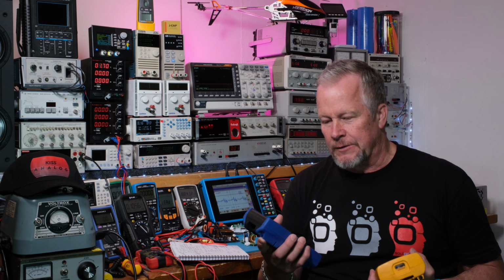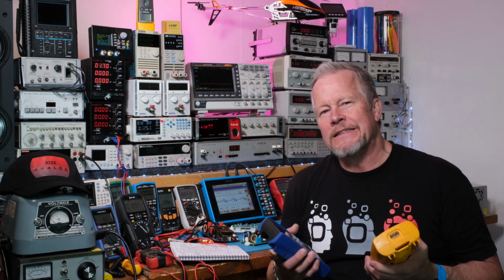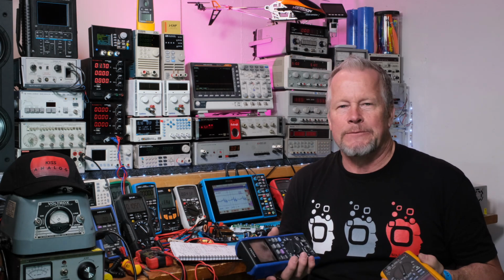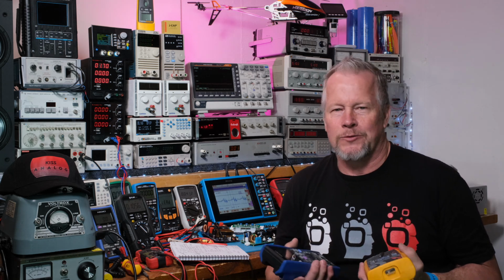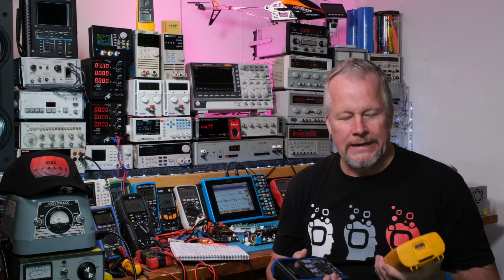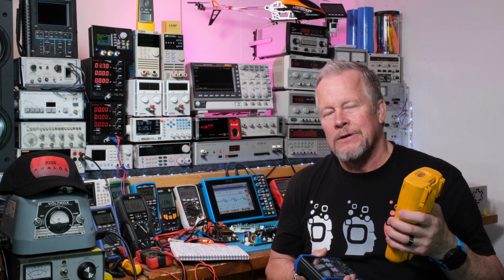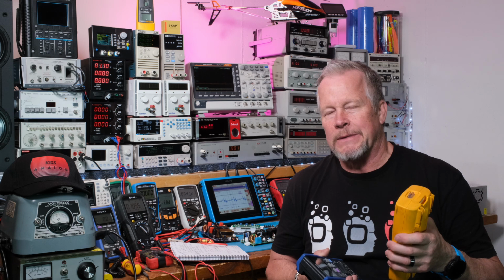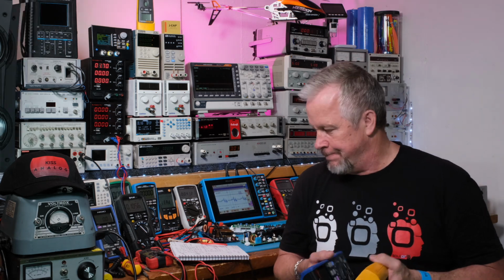But if you want to capture a transient, like an inrush to a power supply, something like that, it's going to happen a lot quicker. The ones with peak measurements are usually set up around, what I've seen seems common, 250 microseconds. So it's quite a bit faster than 100 milliseconds, right? And so you can capture an inrush measurement or a transient voltage. So they have a peak hold as well. That's another benefit you get with some of the higher end meters.